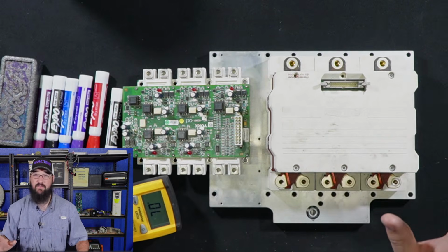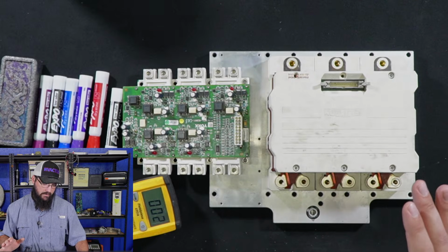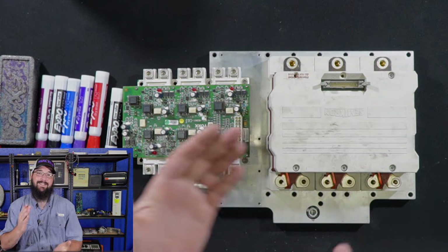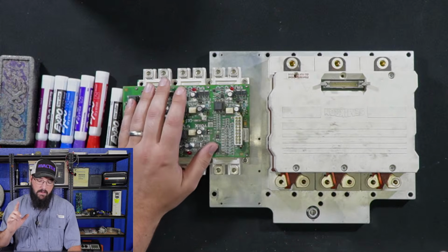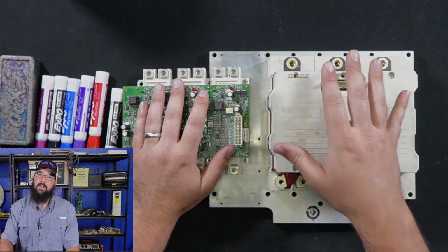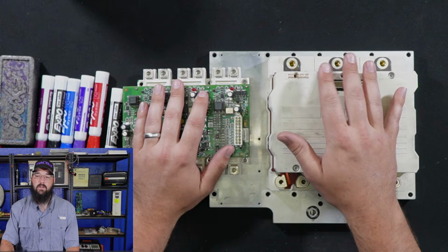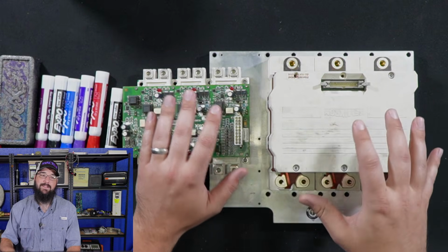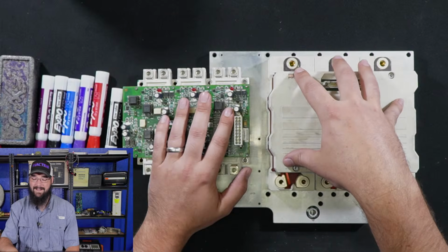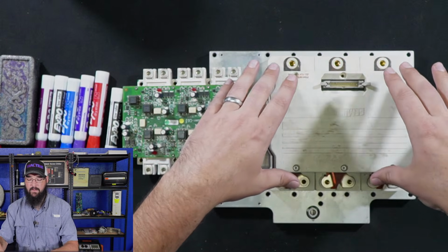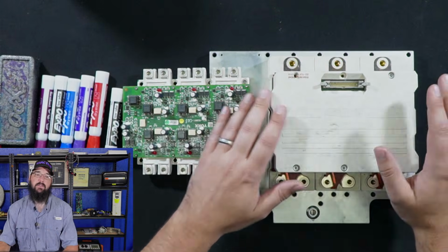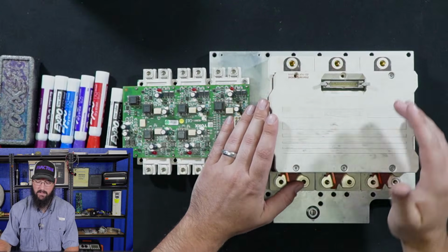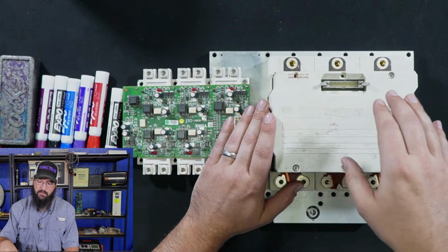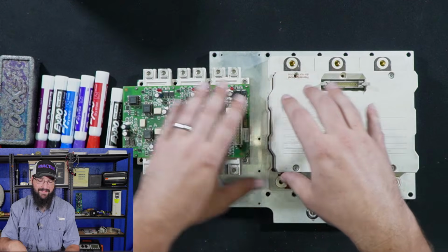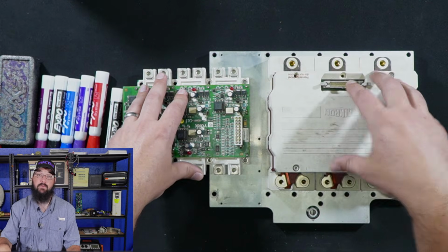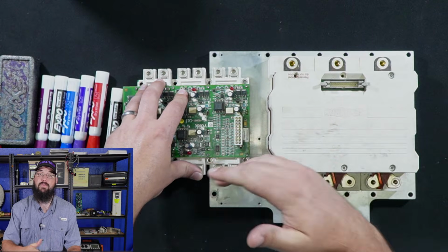Now, this is all just very rule of thumb, generic stuff, right? So what I'm explaining is not just like a hard set rule. But just because these test good does not mean that they are good. Part of what can happen is they still test and they still function, but they're going to start having symptoms like I'm describing. And the point of this test may be that, hey, let's say we're tripping faults, we're blowing fuses, things of that nature.